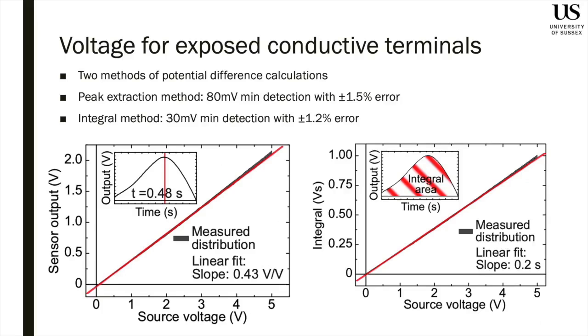So we've done a measurement once for exposed conductive terminals. We repeated this measurement 5 times to calculate the errors, and we varied the voltage of the source under test from 0 volt to 5 volt, and achieved an 80 millivolt minimum detection with a plus or minus 1.5% error. In this way, we basically took the peak value of the transient signal. And we also used the integral method to extract the voltage of the source under test. And then we managed to achieve a better minimum detection voltage of 30 millivolts, and the error was also reduced to 1.2%. And what's interesting is that the source voltage and the sensor output have an extremely linear relationship, which is very desirable for any sensor technology.